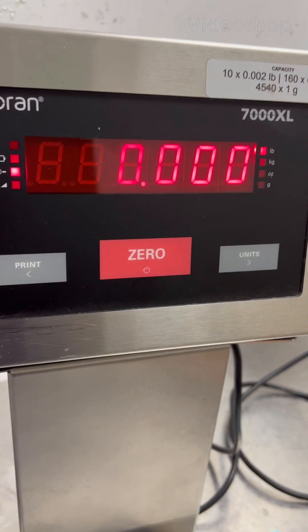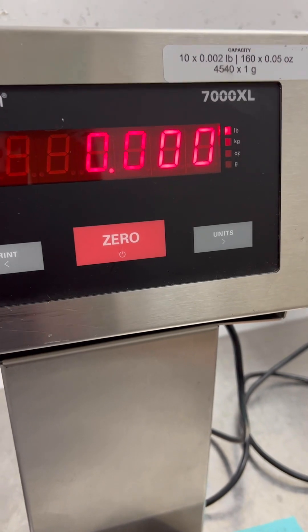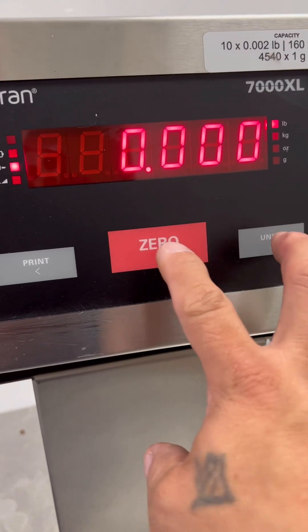This is a calibration adjustment of a Doran 7000XL. It's a little difficult to hold the phone, but you're going to hold these two keys down tightly until you see a P pop up.